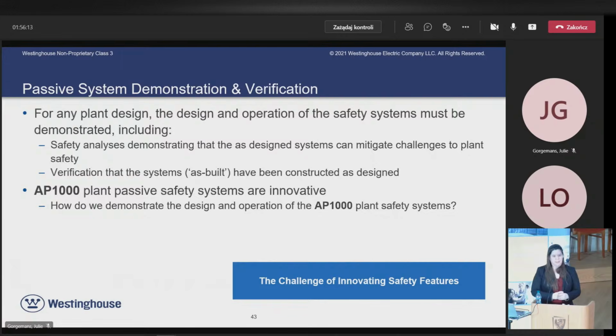The first is what we call the safety analysis side. We first need to demonstrate we have the tools, the computer codes, sufficiently supported by testing and validated by that testing, to predict how passive safety systems will work in the plant. But after that, every time we build an AP1000, we also need to demonstrate that what we have built corresponds to what we assumed in our safety analysis. So there are two steps to the demonstration for each AP1000 unit, that it will operate as we intended when we designed them.